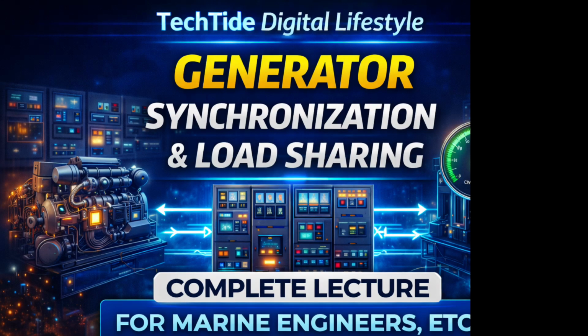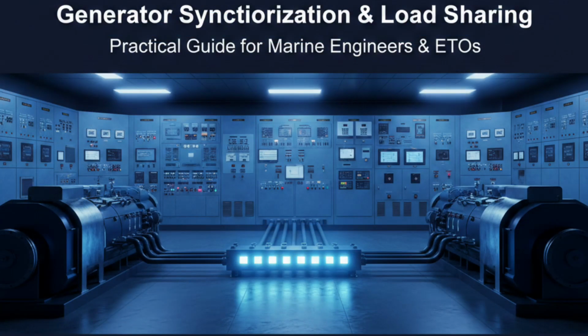In this lecture, we are going to understand one of the most important operations on board any vessel, generator synchronization and load sharing. On a ship, power demand keeps changing. Sometimes one generator is enough. But when load increases, we need to connect another generator to the main switchboard. But we cannot just close the breaker randomly. If we connect a generator without proper synchronization, it can cause heavy mechanical shock, electrical damage, and even complete blackout. That is why synchronization is a very critical process.